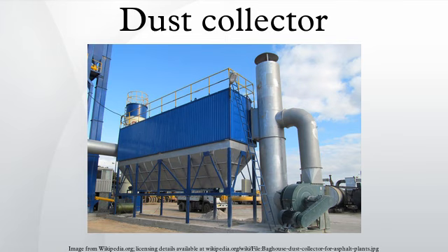A number of designs are available, with capacities ranging from 200 to 2000 ft³/min. There are two main types of unit collectors: fabric collectors, with manual shaking or pulse jet cleaning, normally used for fine dust; and cyclone collectors, normally used for coarse dust. Fabric collectors are frequently used in minerals processing operations because they provide high collection efficiency and uninterrupted exhaust airflow between cleaning cycles. Cyclone collectors are used when coarser dust is generated, as in woodworking, metal grinding, or machining.